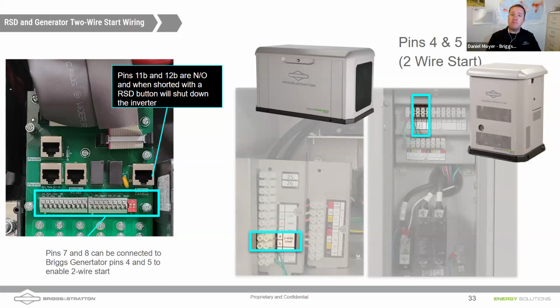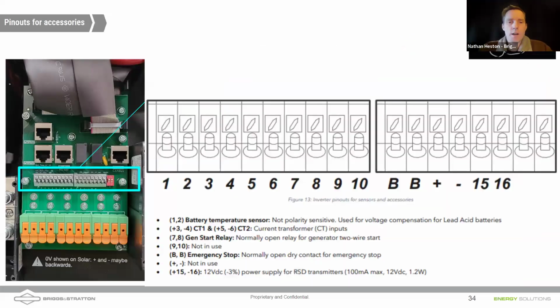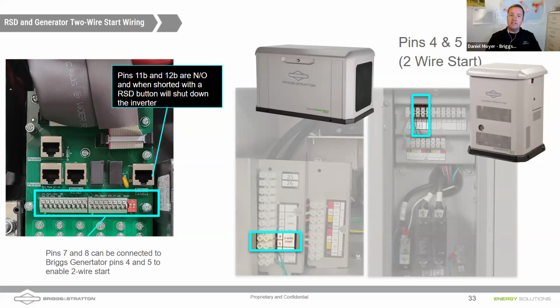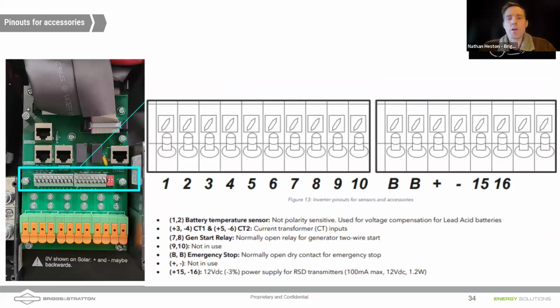We talked about it earlier, but absolutely integrating a generator into a whole home or an off-grid home is key. It's something we've always done. What we can do is run a 2-wire signal to start from the inside of the Sol-Ark using pins 11 and 12, and then we would run them into our generators. You're looking at the horizontal unit and that vertical 13K unit. Pins 4 and 5 would be where we're going to land that. I think you misspoke there, Daniel. It's pins 7 and 8. 7 and 8. 11 and 12 are the rapid shutdown, and they're actually labeled, I think, BB on these inverters. But pins 7 and 8 are ready to go to your 2-wire signal to start, and that'll allow your inverter to automatically start up your generator when those batteries get low.